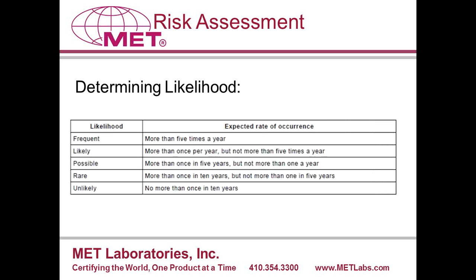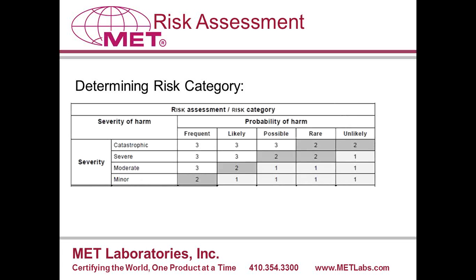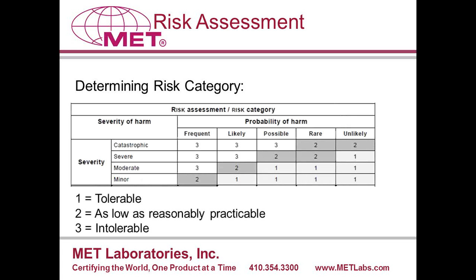After you determine severity, you determine likelihood. Will it happen frequently, several times a year, or probably never, or once in the lifetime of the product? Once you've quantified the risk in terms of severity and likelihood, you can assign to it a risk category. The goal is for all the hazards to be tolerable. If not, something more must be done with the product.